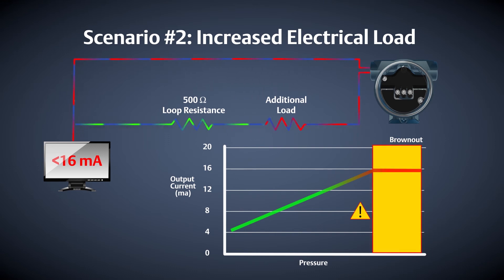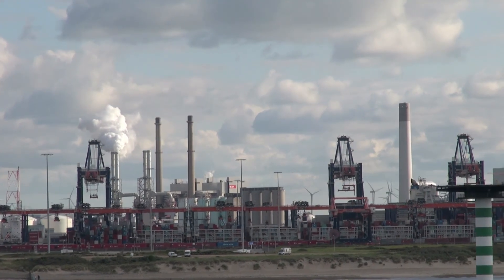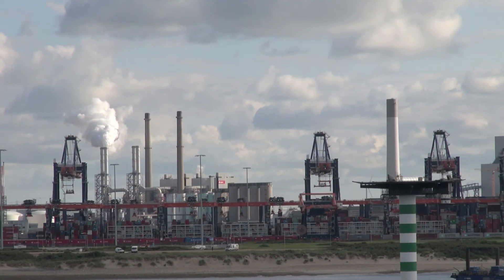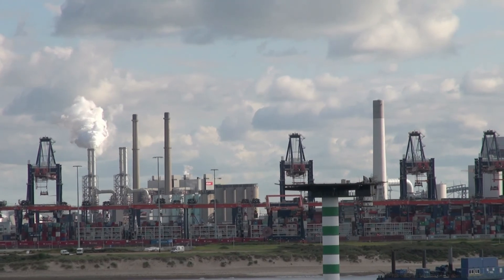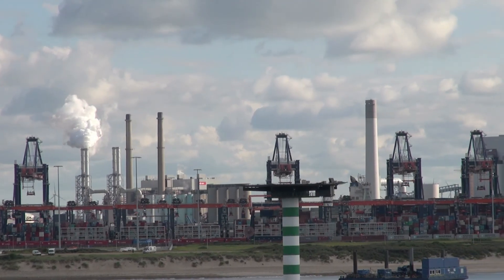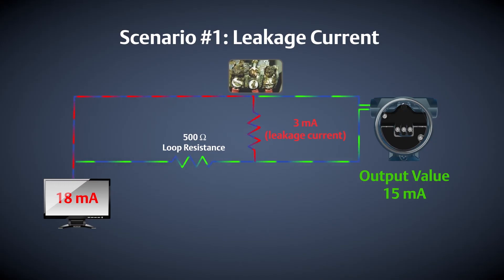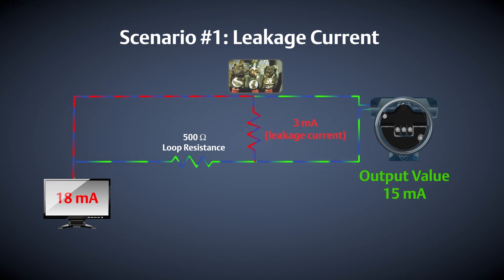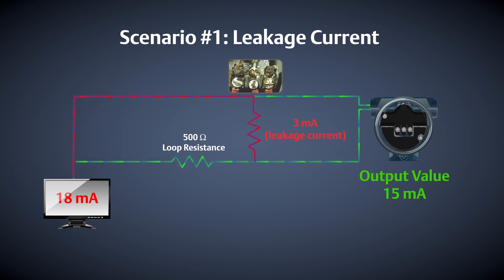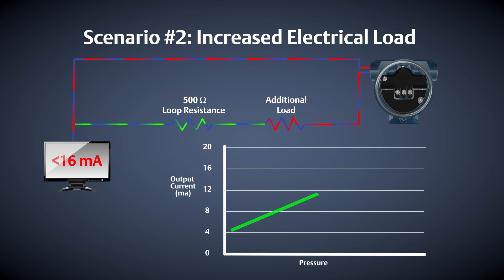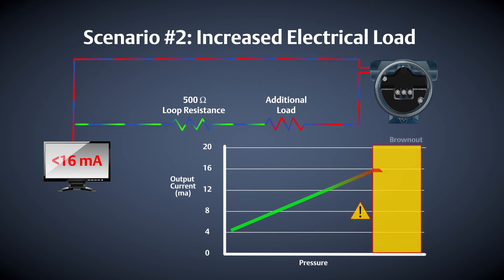In this example, the transmitter is unable to go above 16 milliamps. You don't have the time or resources to perform regular manual loop checks, so you won't know that there is an issue until it's too late. If the milliamp signal is not being conveyed accurately, you may be making adjustments to final control elements that are not required, causing bigger problems. You also may not be able to bring your process to a safe state because you're unable to reach alarm levels.